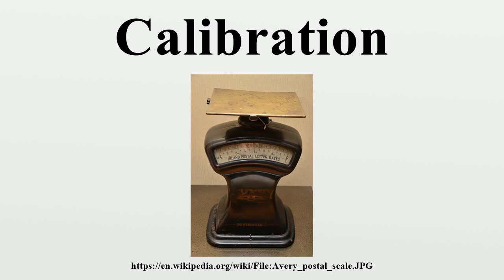The resulting height difference H is a direct measurement of the pressure or vacuum with respect to atmospheric pressure. The absence of pressure or vacuum would make H equal zero. The self-applied calibration would only require the length scale to be set to zero at that same point. This direct measurement of pressure as a height difference depends on both the density of the manometer fluid and a calibrated means of measuring the height difference.